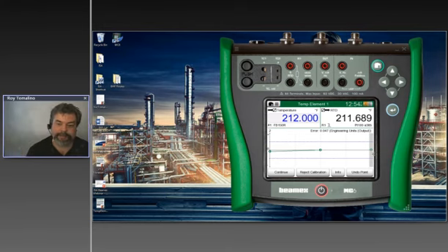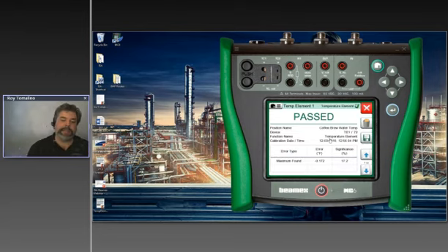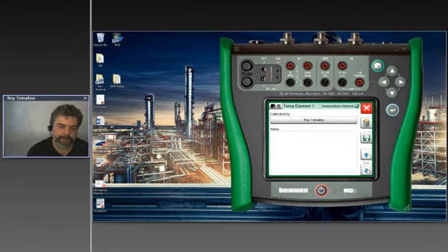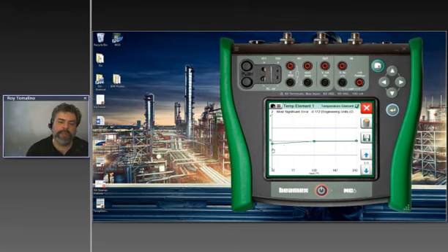Now back to my calibration. I've got my final test point. Let me hit continue. And as soon as I do this, you'll see the countdown, 5 seconds down here on the bottom. And then I've got 0.047 degrees difference, and it's saying that it passed. My most significant error was negative 0.172 degrees Fahrenheit. So one comment about this is the first time that I ran this test, I had a tolerance of 0.5 degree and it failed. Let me arrow down and show you how it failed. On these test points, they were actually quite a bit off the zero. It's because I didn't give it enough delay. When the temperature dry block achieves its temperature, it beeps.